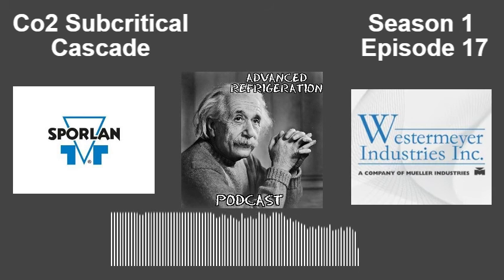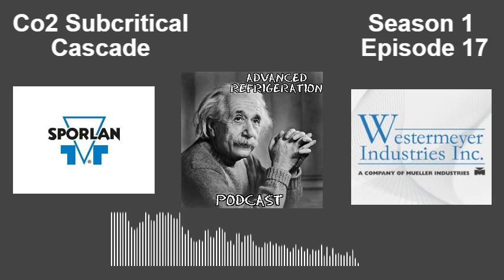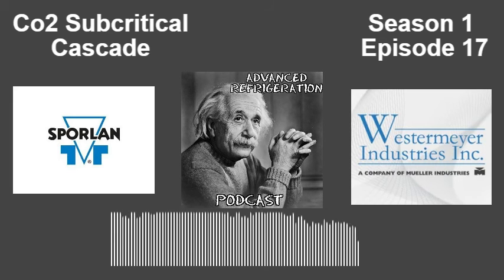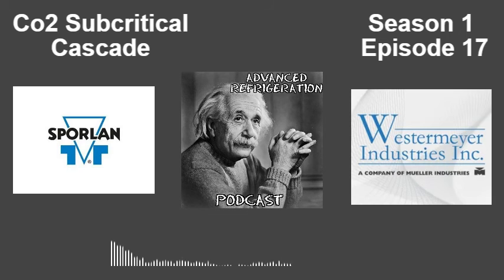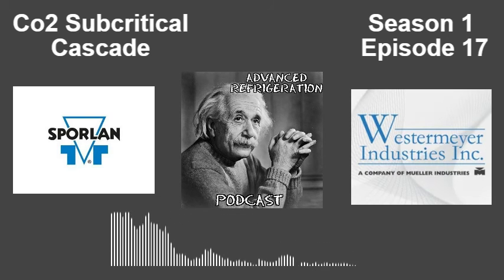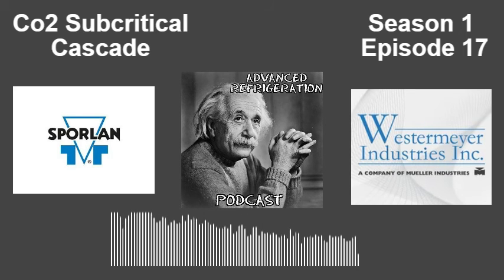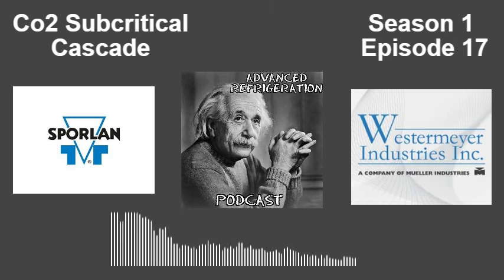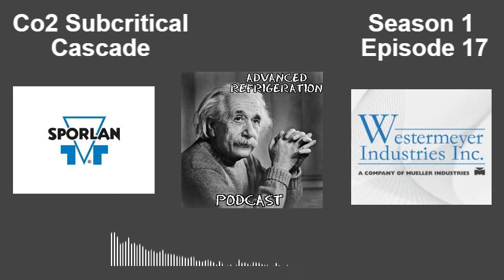I can't attest to that. I've honestly got all the Cascade racks that we have with Bitzers, every single damn one of them. So the only Cascade rack I know is 32 weight on that one, because it's actually 410A scrolls. They're using 410A scrolls for the Cascade side or for the CO2 side? Oh, okay. Which actually Aldi does for their transcritical racks for their low temp. They run CO2. They run 410A compressors.